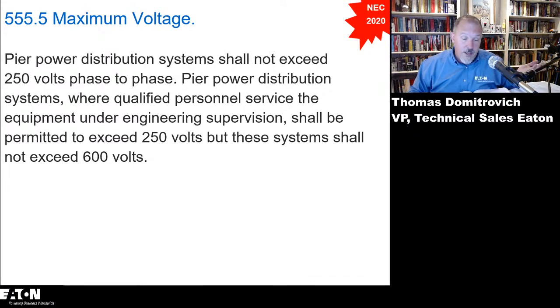And you know what drove that? The alternative energy solutions. They moved all of their stuff above 600 volts. They got rid of the inverter in those. They got rid of the transformer in the inverters. They had to pump that up. So in 555.5, we basically brought that back down again to 600 volts.